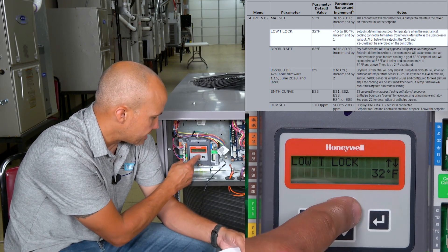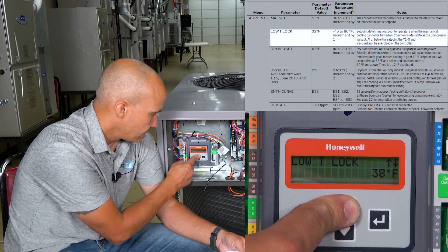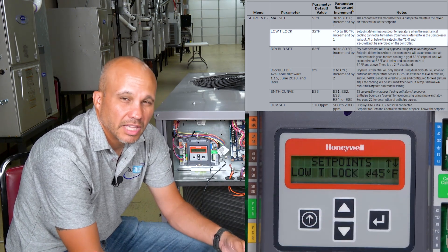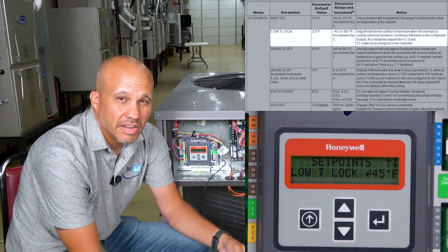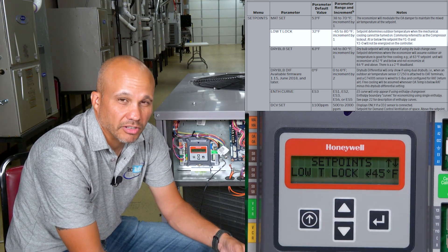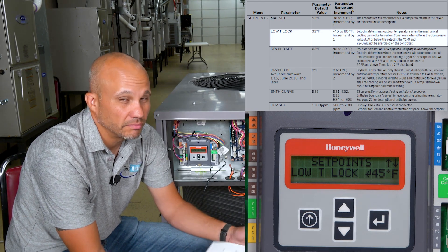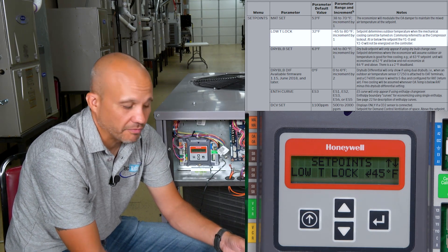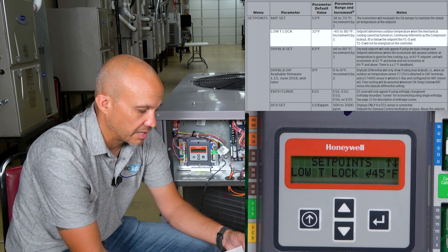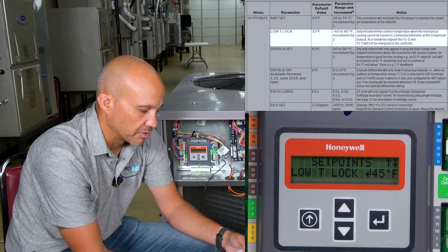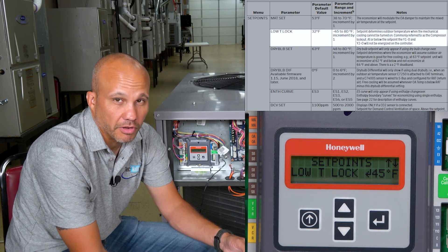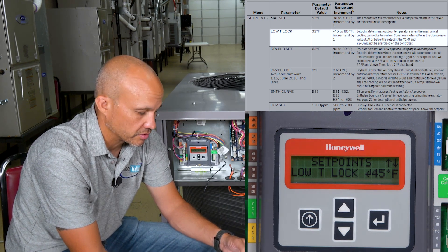Low T Lockout: the default is 32 degrees. I personally like to raise that up to 45. This is the temperature below which it's going to disable the compressors. In my mind, if it's below 45 degrees and I cannot cool the building with the economizer alone, something's wrong. So 45 degrees seems plenty — below 45 I lock out the compressors, above 45 the compressors can run.